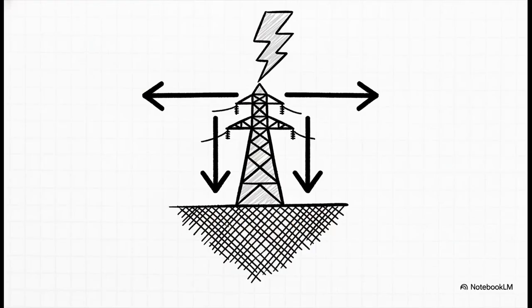And there's an incredible nuance here. The math has to account for the fault current division factor. When a massive fault occurs, not all of that deadly current enters the earth through the local grid. A lot of it actually travels back along overhead static wires or feeder neutrals. By calculating the exact symmetrical grid current, meaning only the specific portion of the fault current that actually flows between the grid and the surrounding soil, engineers avoid massively over-designing the system. This saves millions of dollars in copper while maintaining strict life-saving safety standards.